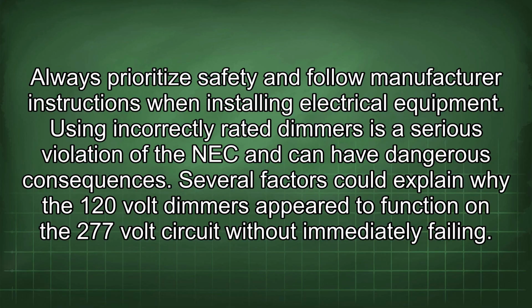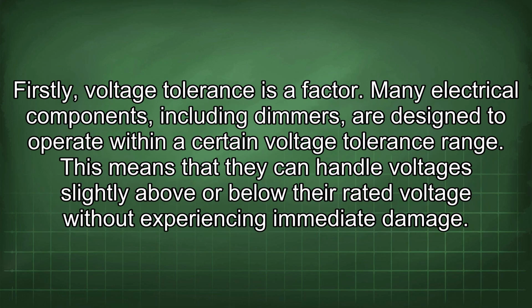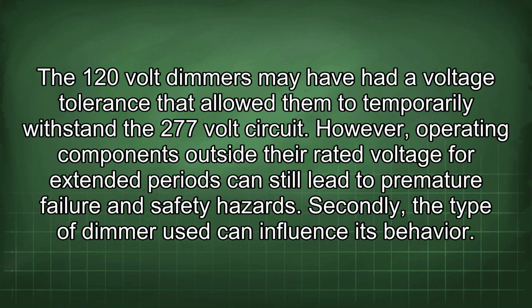Several factors could explain why the 120-volt dimmers appeared to function on the 277-volt circuit without immediately failing. Firstly, voltage tolerance is a factor. Many electrical components, including dimmers, are designed to operate within a certain voltage tolerance range. This means that they can handle voltages slightly above or below their rated voltage without experiencing immediate damage. The 120-volt dimmers may have had a voltage tolerance that allowed them to temporarily withstand the 277-volt circuit. However, operating components outside their rated voltage for extended periods can still lead to premature failure and safety hazards.